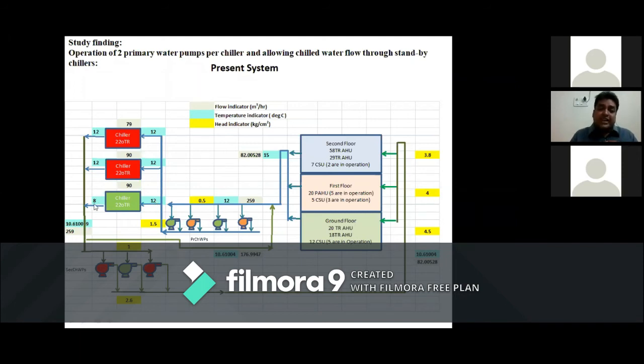Going out, the water is coming at 8 degrees centigrade. Now this 8 degrees water has to go back to my building. But if you see here, the water is going at 10.61. That means immediately after my chiller there is a drop of 2 degrees centigrade, and the capacity is 220 TR.